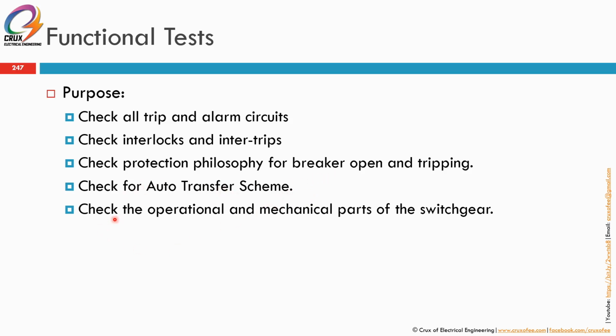Okay, and then check the operational and mechanical parts of the switchgear. So this functional test will also verify the operational and mechanical parts of the switchgear. So these tests are still being done offline, meaning the switchgears are still not online yet. So you are only testing the switchgears with auxiliary supply 110 DC or 110 AC, 240 AC from external supply.